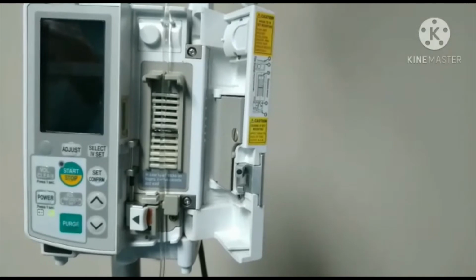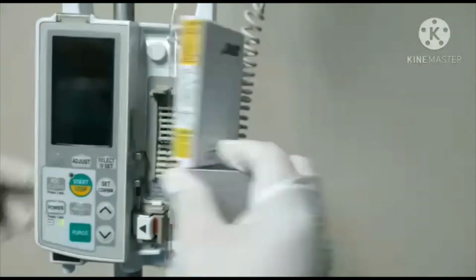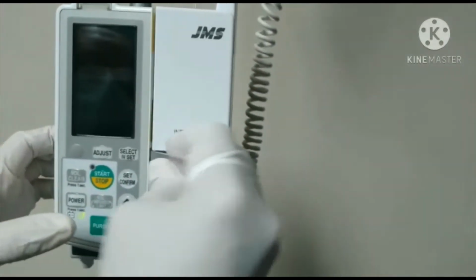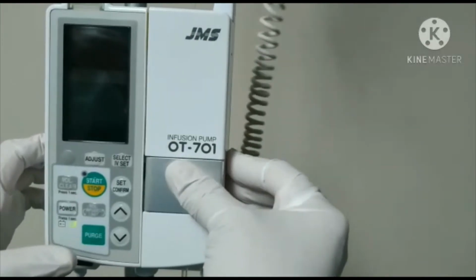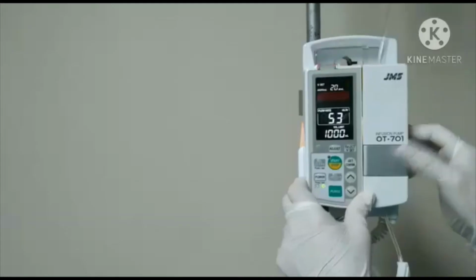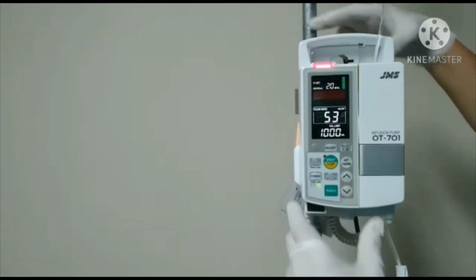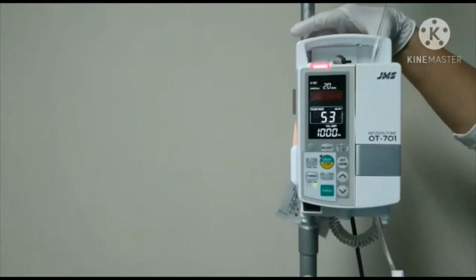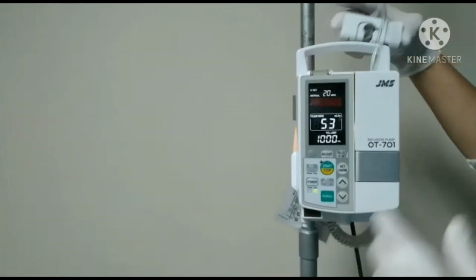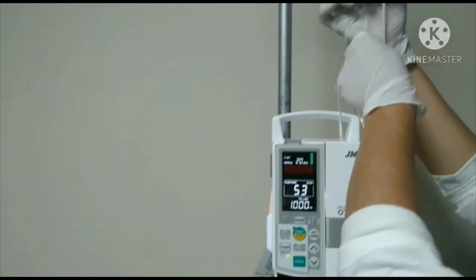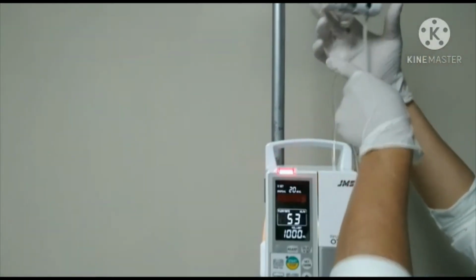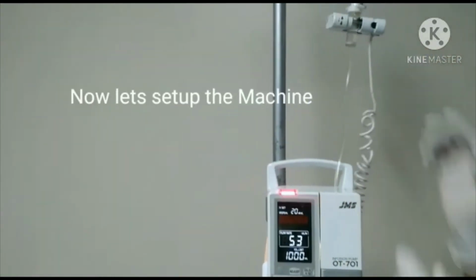When the tube is completely secured in the tube guide, the pump door is closed and the programming can begin. Be sure to hear the click as the door lever is closed. The pump can then be powered on and the drip detector put in place while it completes its booting up. The IV clamp is rolled open to prevent occlusion before the patient. Setting up the machine is fairly intuitive.